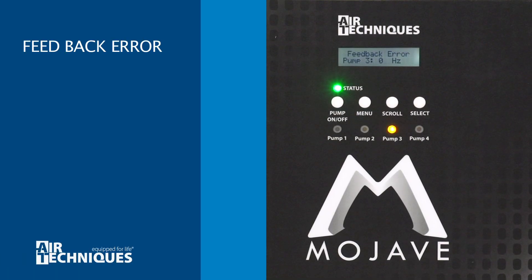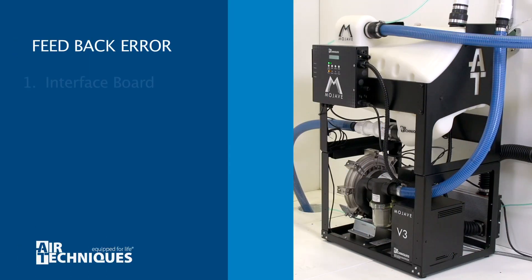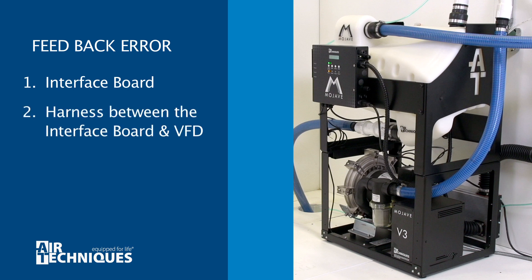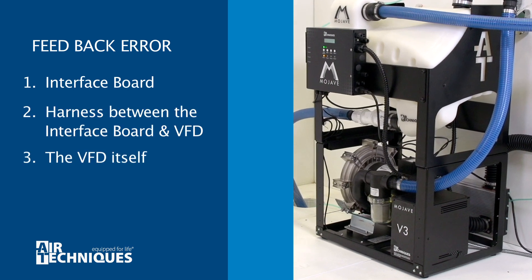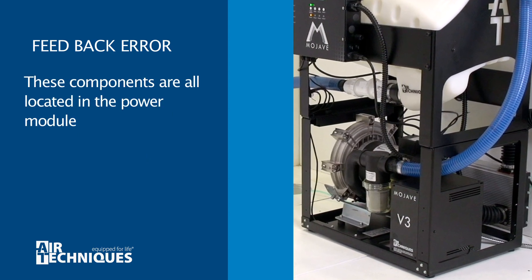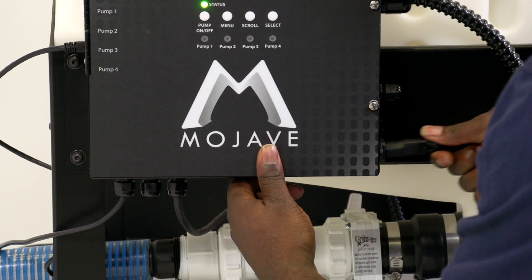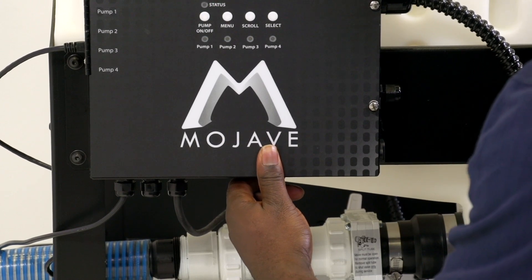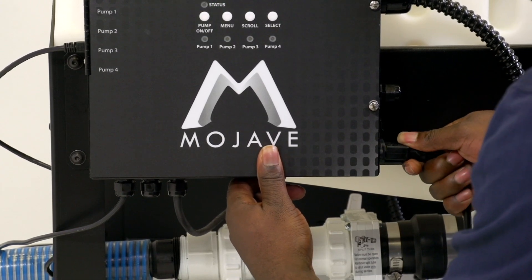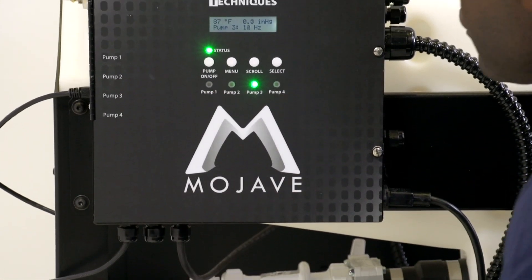When a feedback error occurs, this will usually cause the pump to shut down. The possible problems are the interface board, the harness between the interface board and the VFD, or the VFD itself. All three components are found in the power module. This error will reset itself when the automatic self-diagnosis feature runs, when the pump is disconnected then reconnected, or when power to the MMC is cycled.